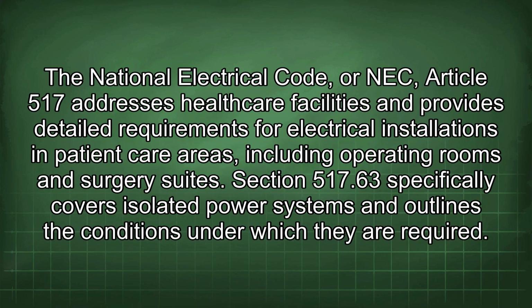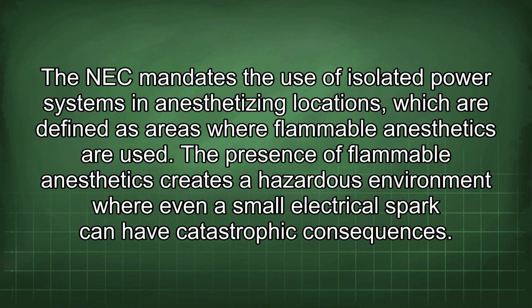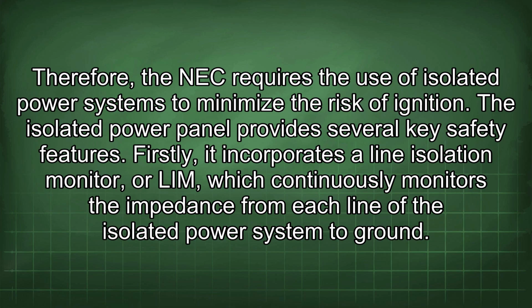The National Electrical Code, or NEC, Article 517 addresses healthcare facilities and provides detailed requirements for electrical installations in patient care areas, including operating rooms and surgery suites. Section 517.63 specifically covers isolated power systems and outlines the conditions under which they are required. The NEC mandates the use of isolated power systems in anesthetizing locations, which are defined as areas where flammable anesthetics are used. The presence of flammable anesthetics creates a hazardous environment where even a small electrical spark can have catastrophic consequences. Therefore, the NEC requires the use of isolated power systems to minimize the risk of ignition.